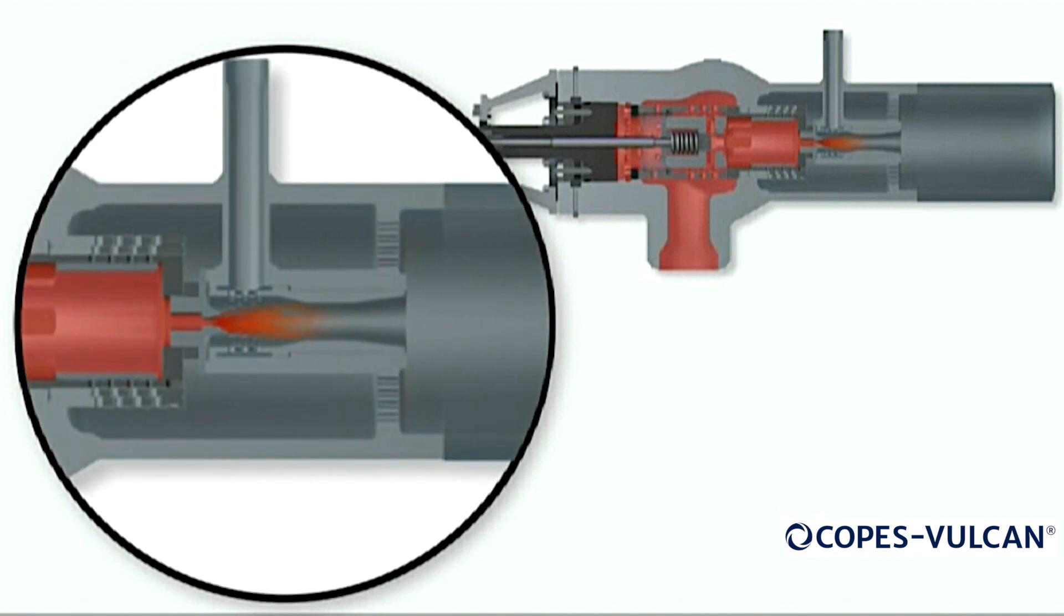Now with the pilot plug open, high pressure inlet steam has flooded the underside of the main plug, and the steam atomizing unit is now operating in preparation to receive the incoming cooling water from the water control valve.